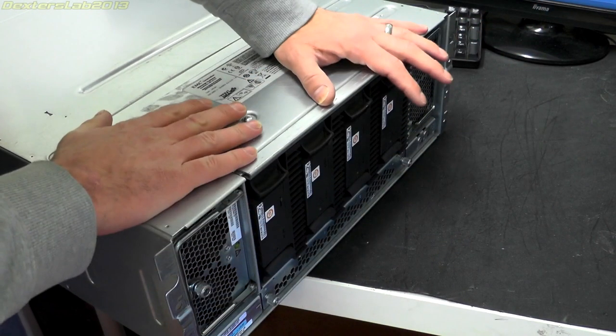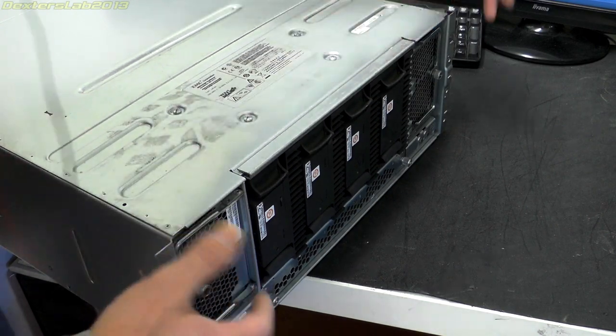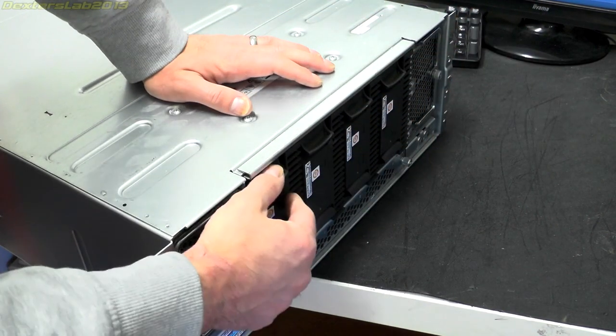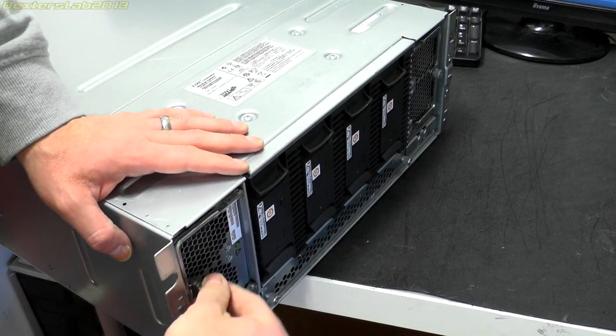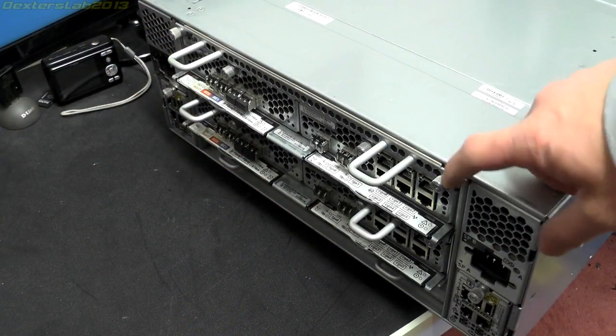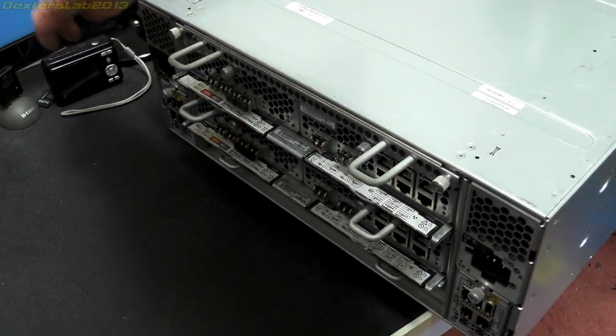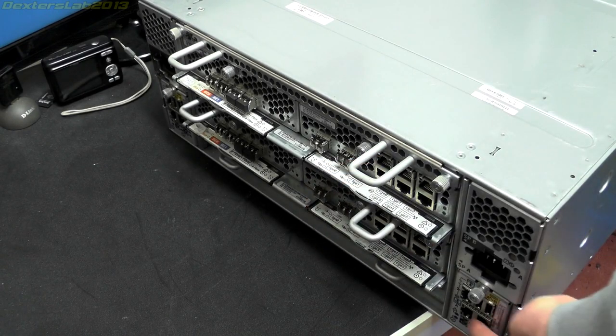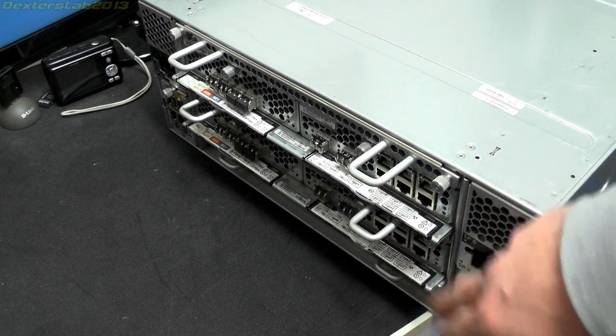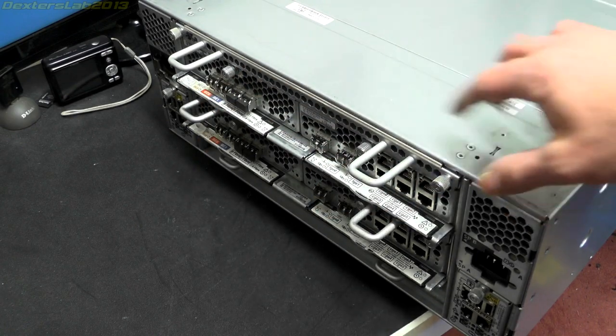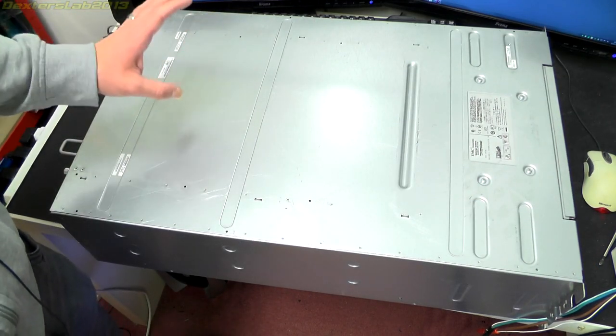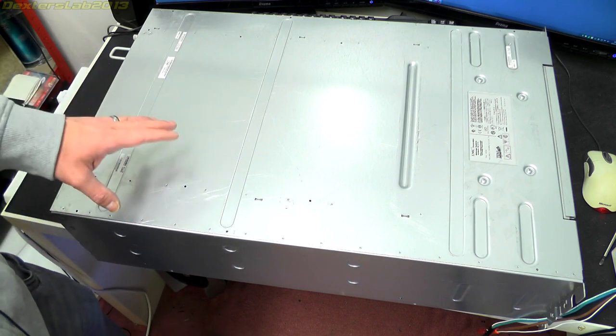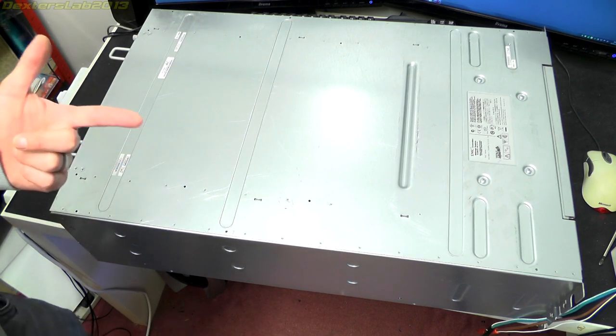And there you go you can see the front a little bit better, we've got ventilation ports on each side. The whole system is made to be fault tolerant and redundant so everything is duplicated. These are the power supplies one on each side, these black units are the cooling fans so these plug in, these parts here are the power supplies. So that's one of the power supplies and around on the back we've got the power inputs for the two power supplies one there, one around here. We've got the two processing boards and we've got auxiliary connections which allow you to connect these boards to local networks and things like that. All these ports are here for the interconnections between this unit and the rest of the actual system.